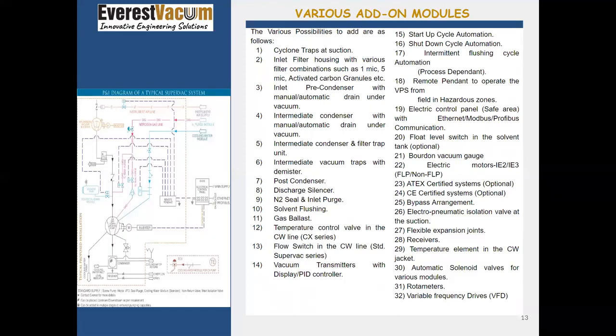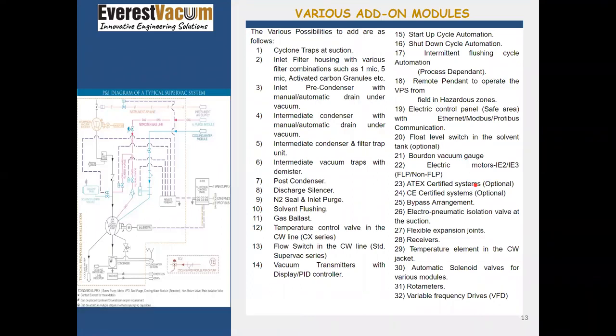Then there can be some Bourdon gauges present at the suction of the vacuum system in certain configurations. For electrical motors, it is by default IE2 in flame-proof construction and IE3 in non-flame-proof construction, premium efficiency motors. Then there are ATEX certified systems, CE certified systems, bypass arrangements to reduce the vapor load on the machines, and electro-pneumatic isolation valves to separate our vacuum pumping system from the client's process. Then there is the availability of flexible expansion joints, bellows, the receivers, and a temperature element in the cooling water jacket to automatically trip off or cut off the pump in case the temperature exceeds the preset levels. Then there are rotameters and variable frequency drives available. So these all are the add-on modules that Everest has.